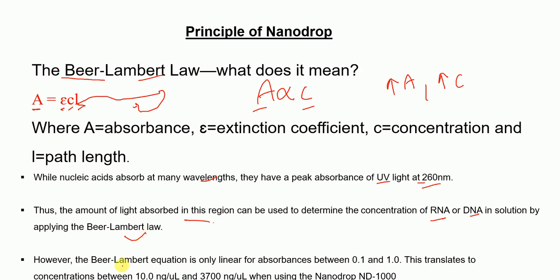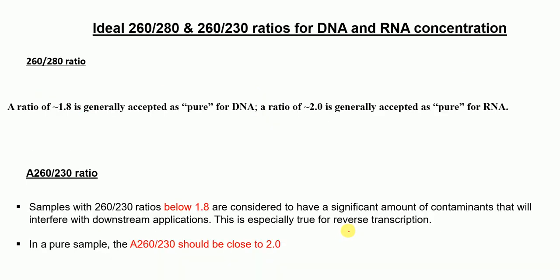However, the Beer-Lambert law equation is linear only for absorbances between 0.1 and 1, which means that only concentrations from 10 nanograms per microliter to 3700 nanograms per microliter can be accurately measured using nanodrop instrumentation.